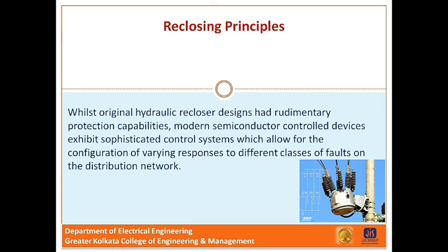Recloser with sensitive arc fault protection capable of detecting 500 mA and below are used as a fire mitigation technique, as they provide an 80% risk reduction in fire starts. However, they are never to be used as reclosers in this application, only as single shot distributed circuit breakers which allow for sensitivity to verify the existence of these faults.